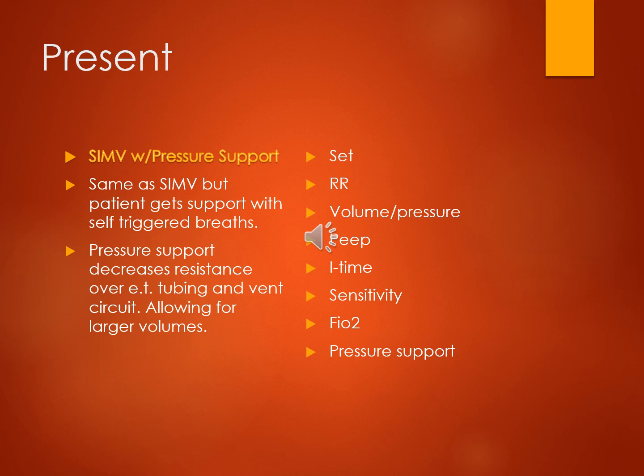In between those breaths, the ventilator will allow them to take those breaths without being impeded, right? So it's not going to cycle another breath while that patient is in their breath phase. So that keeps the patient from stacking breaths. If they were in their own breath pattern and they were generating, say, 300 mLs, we wouldn't want the ventilator to step on that breath and give them another 500 on top of that. We want it to wait, and depending on the algorithm of that specific ventilator, the patient will be able to finish their breath, or almost completely finish their breath, before the ventilator cycles another breath.